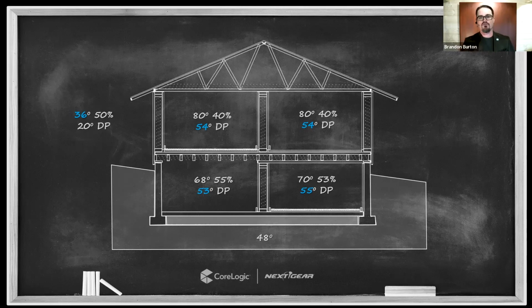And then our evaporation rates really slow down, the indoor humidity begins to decrease, and we go from 80-40 inside down to 80-30 or down to 80-25. And as that indoor air begins to become drier, the indoor dew point begins to drop. And then once we get down to an indoor dew point of like 20 degrees, all of a sudden everything else that was cold begins to dry. Wouldn't it be nice if I didn't have to wait 2 or 3 days for those more difficult materials to begin to dry because they're cold?